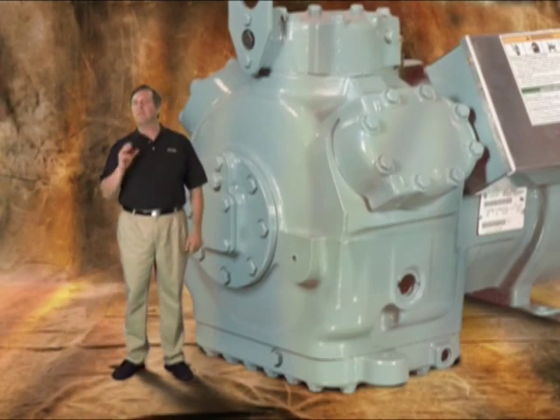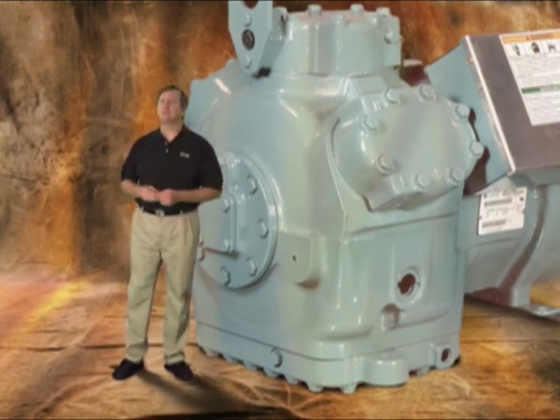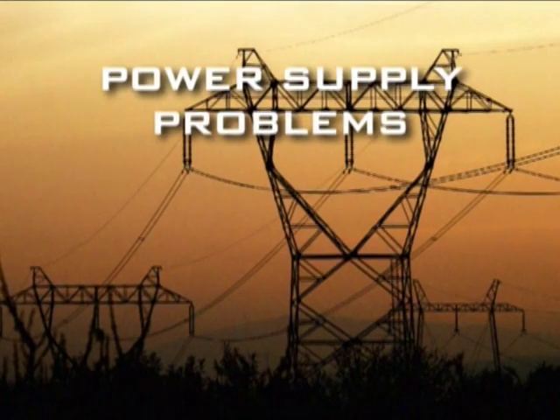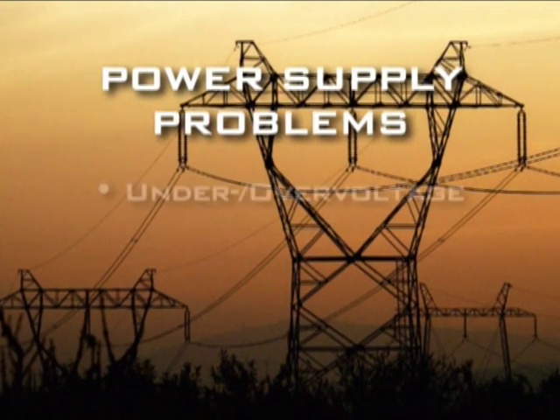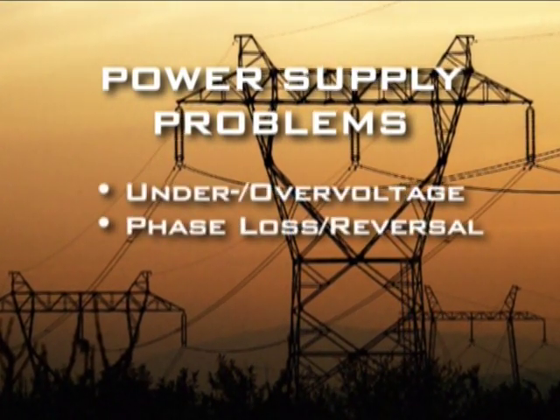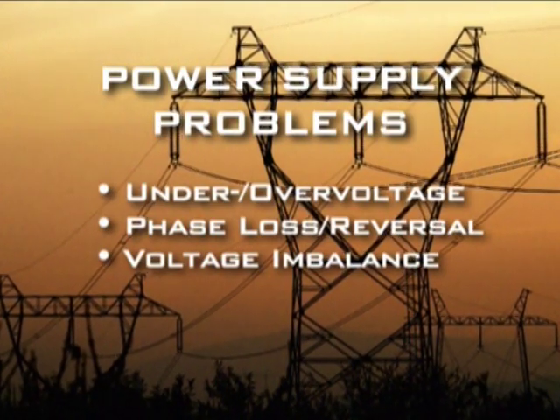The compressor is the most critical part of your air conditioner or refrigeration system. Unfortunately, it's also the most vulnerable. That's because even relatively minor problems with a three-phase power supply can lead to premature compressor failure. Power supply problems are surprisingly common. Typical problems include under and over voltage conditions, phase loss or phase reversal, and voltage imbalance. Let's take a closer look at each problem.